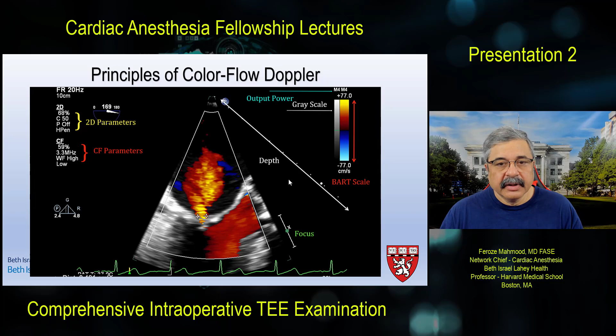This demonstrates the grayscale, and this demonstrates the BART scale, which we will talk about in a second. And this is your upper limit of flow, which is 0.77 meters per second in the direction of the transducer, and 0.77 meters per second away from the transducer is the upper limit of velocity that you can detect. And this is, of course, the output power.